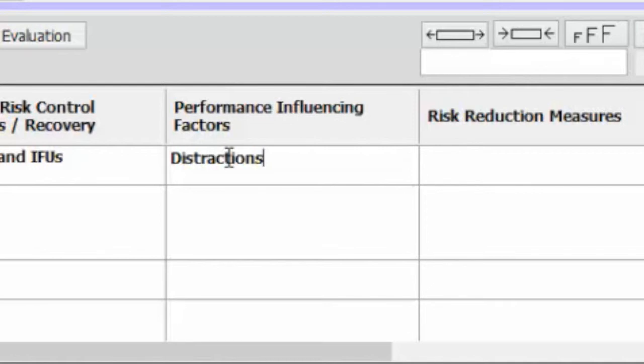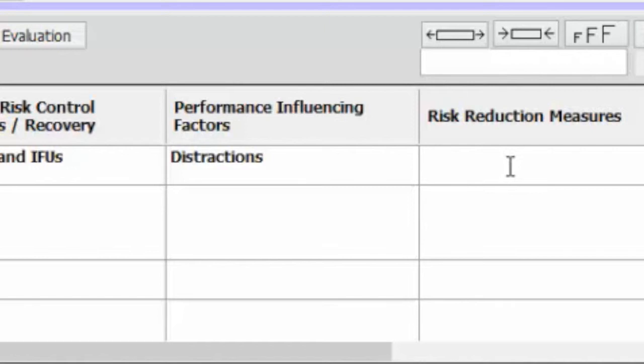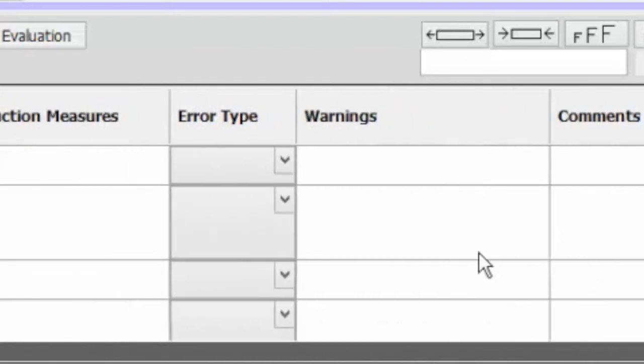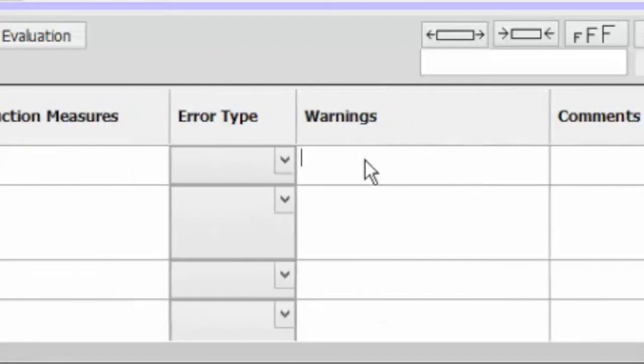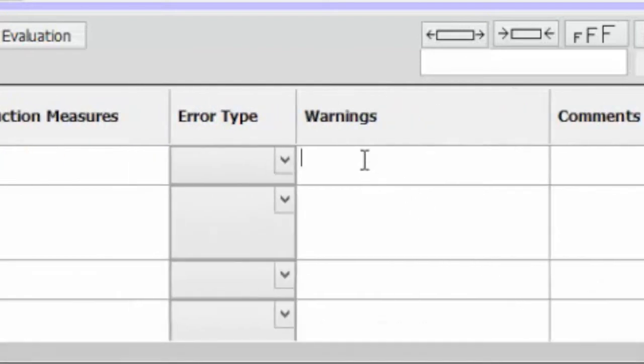So if we think that our device is going to be used in a distracting environment we would want to make sure that there is a risk reduction measure introduced here. So what we would say is that in the instructions for use we might say that this is a critical step and therefore we want to make sure that there are no distractions when it's being carried out. So this will be in a checklist and we might want to insert a warning there also. So okay so like this is a critical step would be a warning.